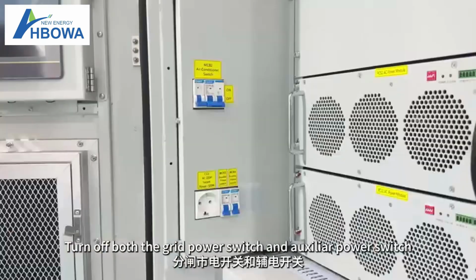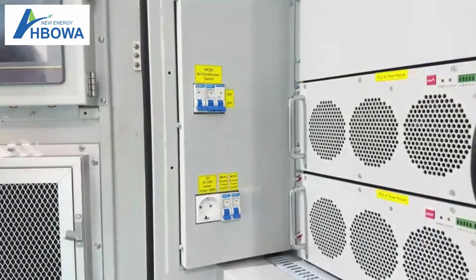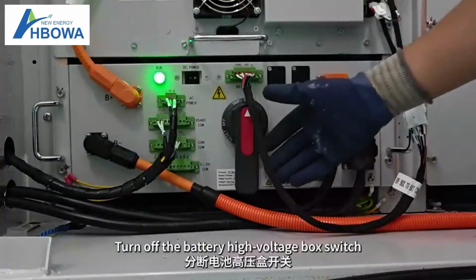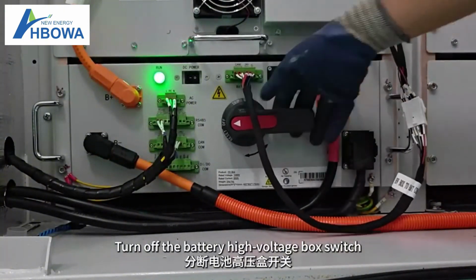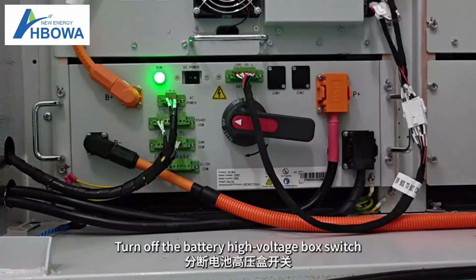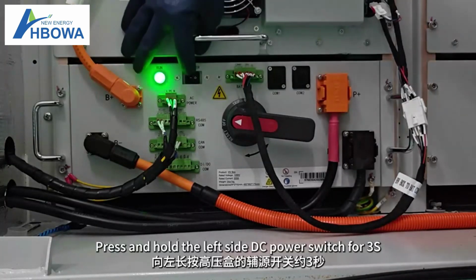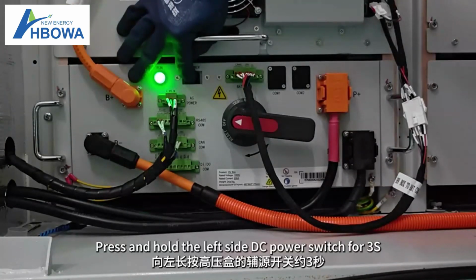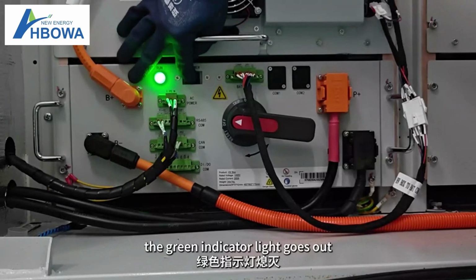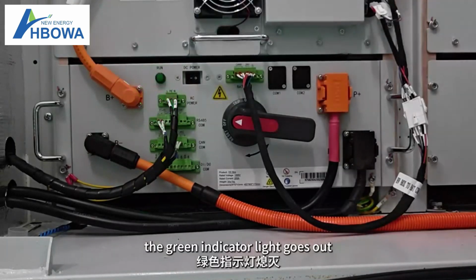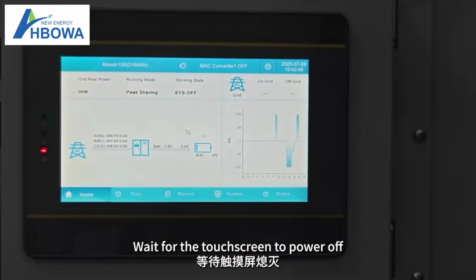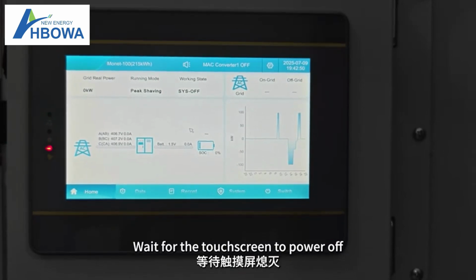Turn off both the grid power switch and auxiliary power switch. Turn off the battery high voltage box switch. Press and hold the DC power switch to the left for 3 seconds. The green indicator light goes out. Wait for the touchscreen to power off. The device is shut down.